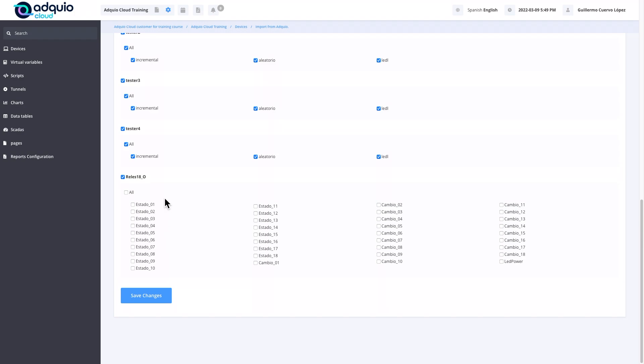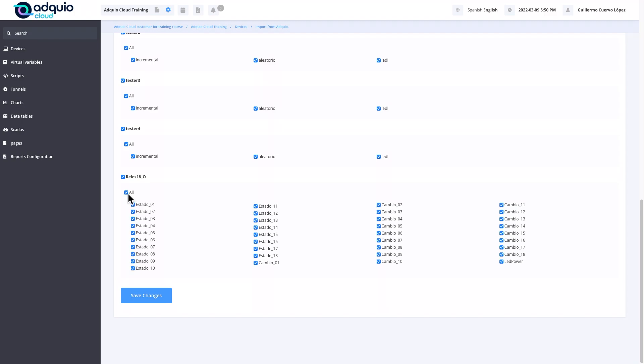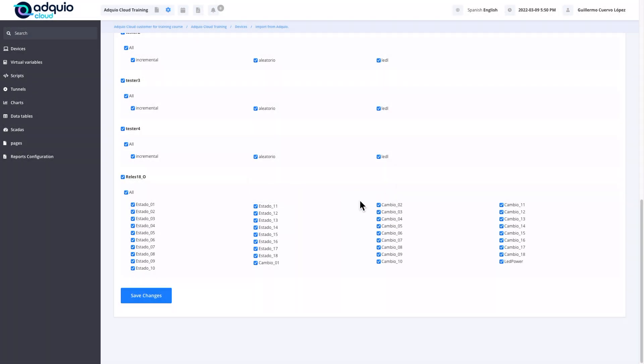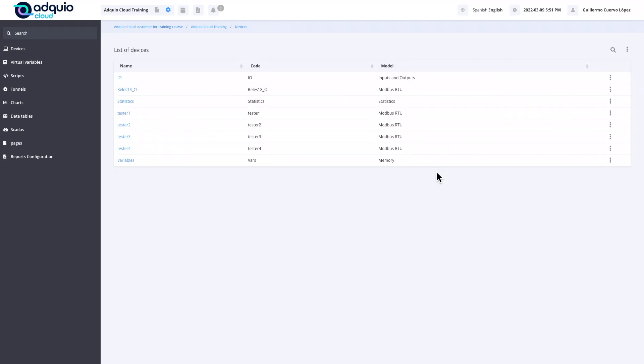Finally, we have a device that includes 18 relays that will be used to do writing tests on external devices through buses. We have 18 states that tell us if it is activated or deactivated with a 1 or 0, and we also have the possibility of change registers. In this case, every time we write a 1 in the change variable, it inverts the state it currently has, varying from 0 to 1. We also have the possibility to control one LED. All Adquio expansion devices have an online LED, and through this register we can turn that LED on and off. We are going to save the changes.